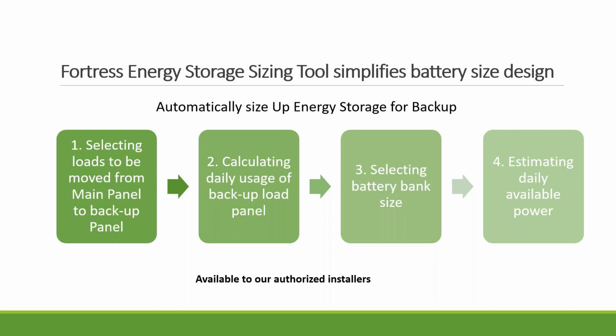We have an Excel sheet to show you, to help you go through the possible circuits you have. Then based on what you selected, you can calculate your daily usage of the backup load panel. And then third step, based on the days of autonomy the customer wants to achieve, plus the customer's budget, you select the battery bank size. At the end, we also recommend you do a production estimate and explain to the homeowner or your facility owner what they can expect in different months from the PV plus storage.